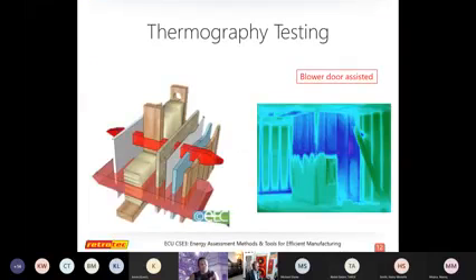So this is a photo that we took a while back. This is an elevator at the top floor. This is what I was talking about earlier. As we are running our fans to depressurize the building, we can see this cold winter air being pulled in. That's what the blue stuff is on this elevator shaft. So we're able to identify that right above this elevator is an area that we would want to seal to make this building tighter.